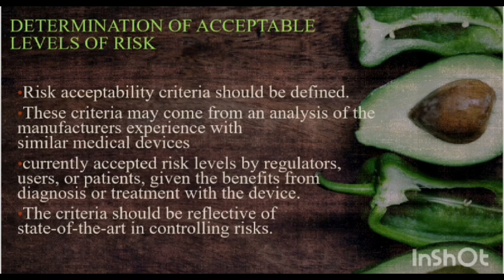Then the currently acceptable risk levels by the regulators, users or patients, given the benefits from the diagnosis or treatment with the device. So the comments and reviews given by the patients or any users of the device should be included. The criteria should be reflective of the state of the art in controlling risks.